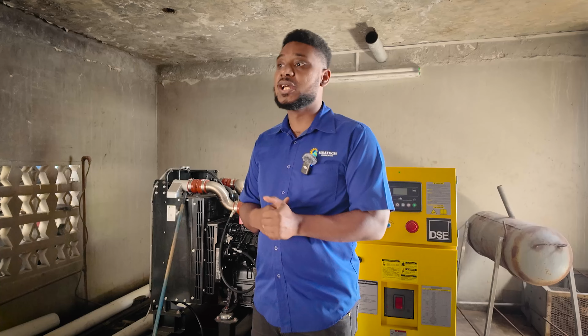These generators can run continuously, I would say up to 10 days continuously, 24/7. I wouldn't go further than that, because I would then recommend that a service is performed - change of oil and filters. We've done this kind of service for clients who've had to run their generator consistently.